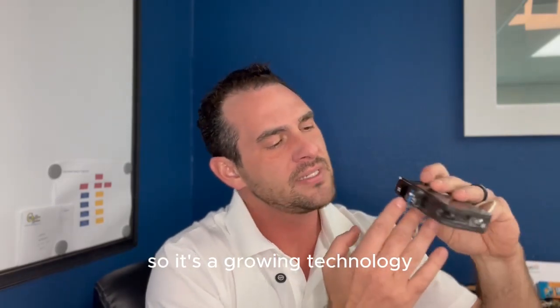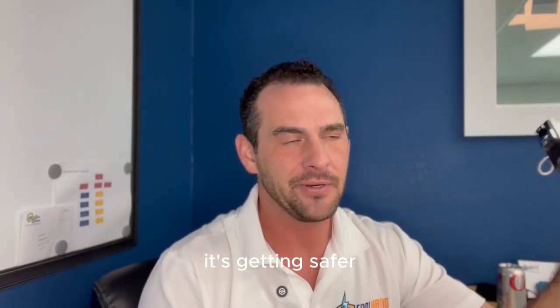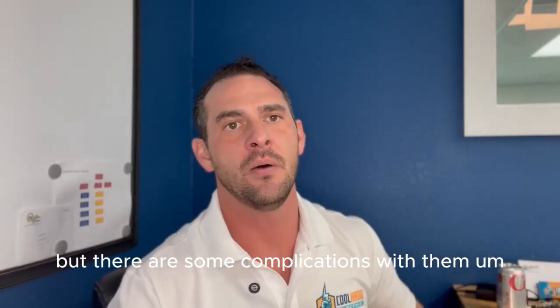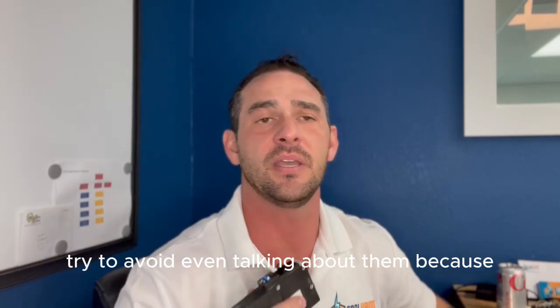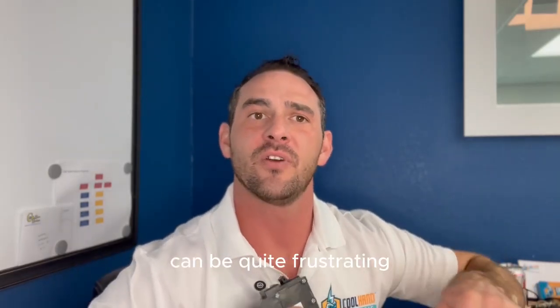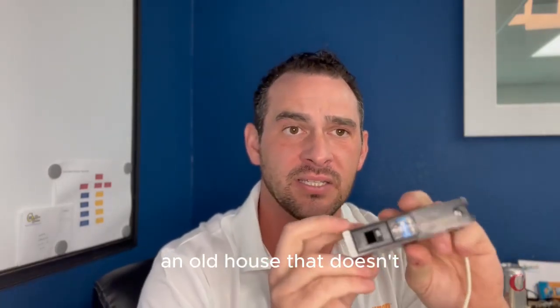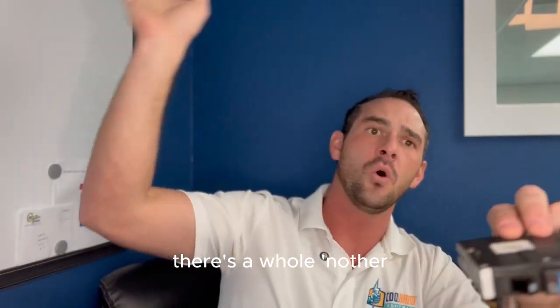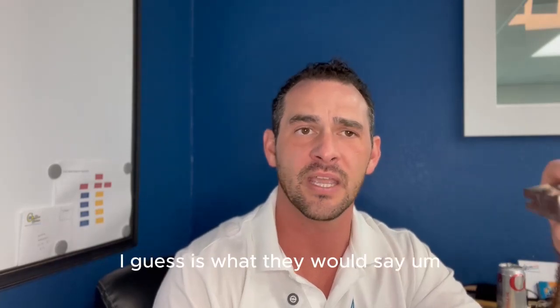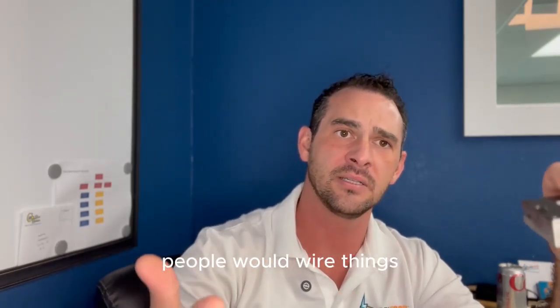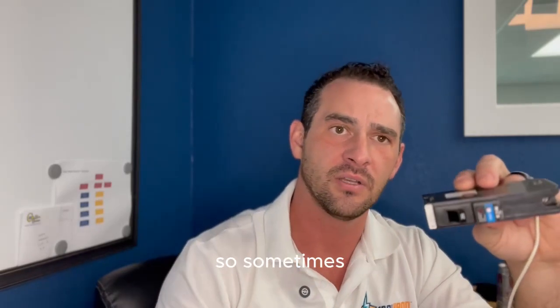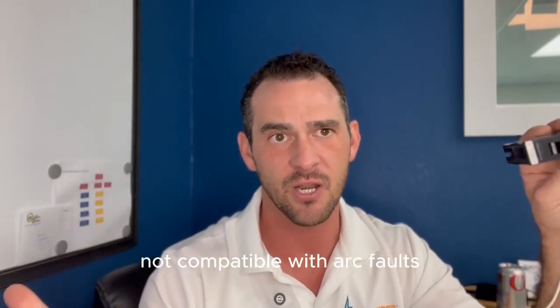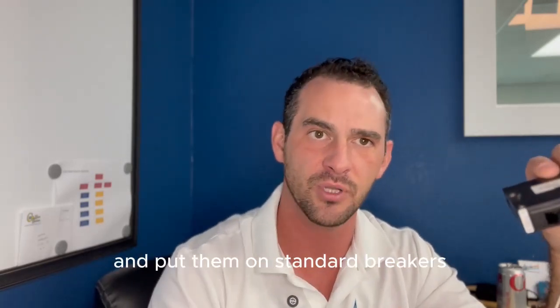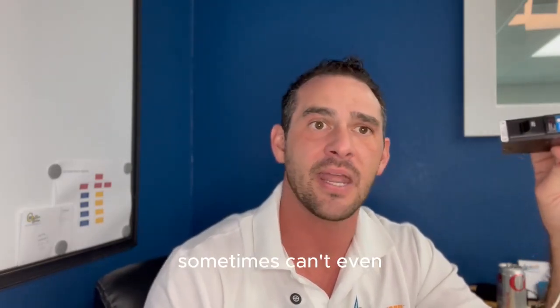So it's a growing technology. It's getting better. It's getting safer, but there are some complications with them. A lot of electricians try to avoid even talking about them because the warranties and the callbacks can be quite frustrating, and a customer can get frustrated with it. And when you upgrade an old house that wasn't wired for arc faults, there's a whole other bag of worms, I guess is what they would say. People would wire things on your three-ways, especially in older houses, that just does not comply with arc faults. So sometimes you've got to run new wiring, or it's like, hey, this is not compatible with arc faults. We try it out, and then we have to take some of them off and put them on standard breakers, just because older wiring sometimes can't work with it.